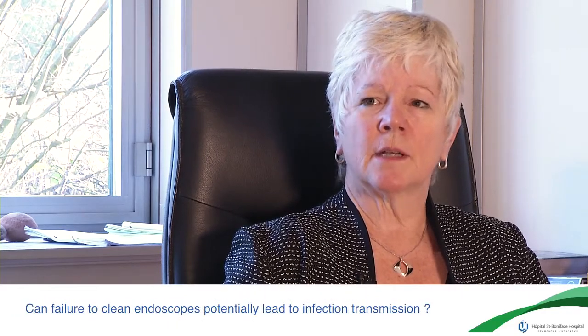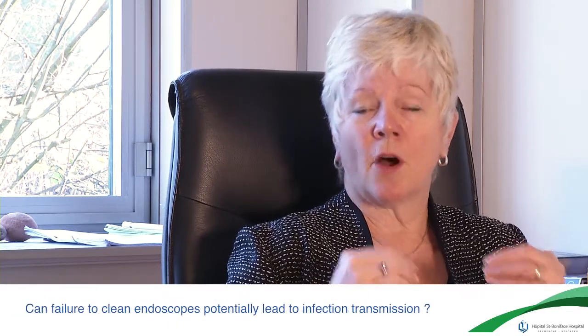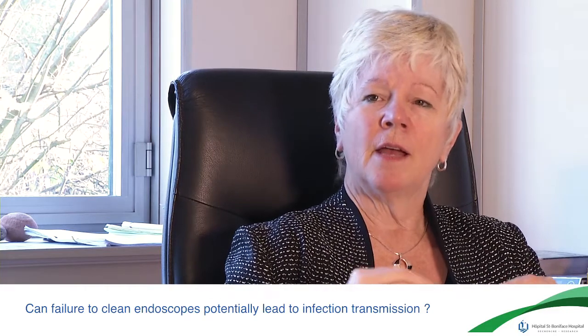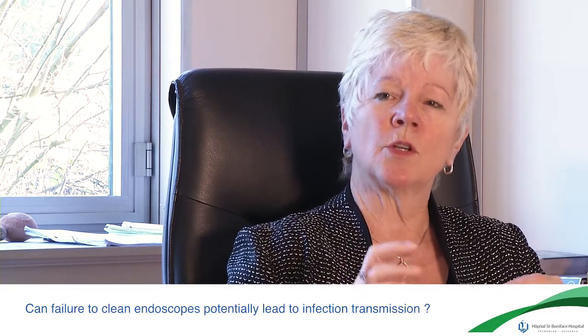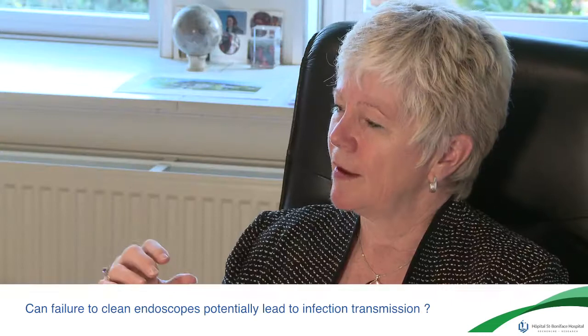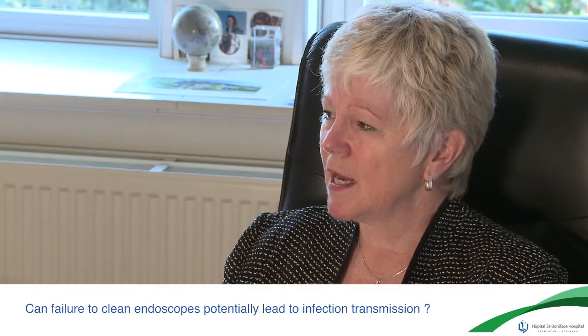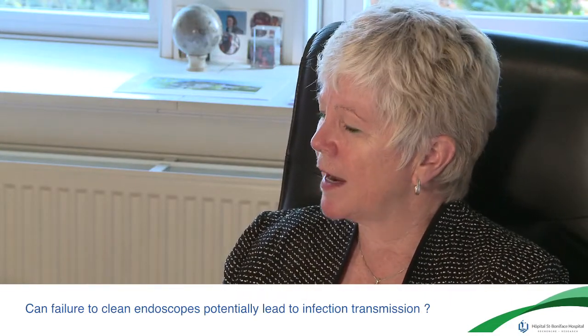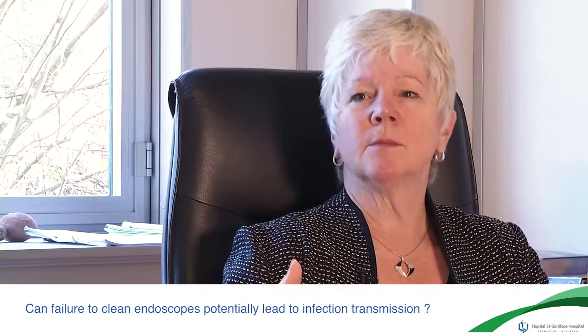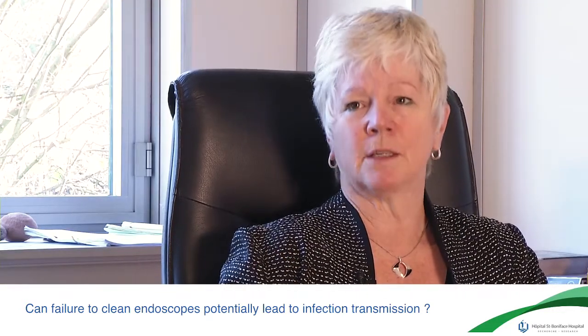So can failure to clean endoscopes potentially lead to infection transmission? Failure of cleaning has actually been shown in several of the outbreaks that have occurred to be what was thought to be the basis of the contamination in the scopes. In other words, they weren't cleaned properly, therefore high-level disinfection failed, and that resulted in surviving organisms that ultimately were shown to infect patients.